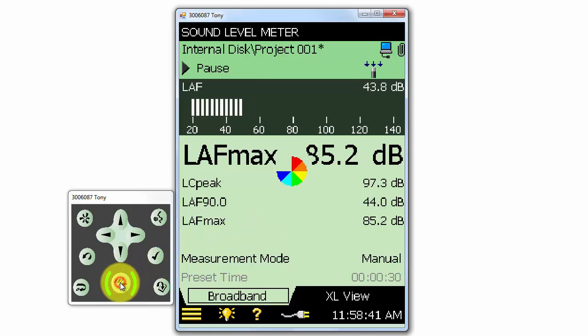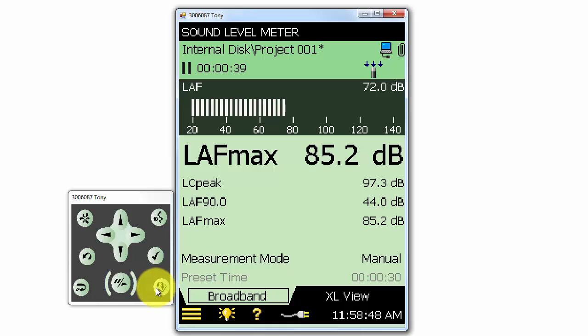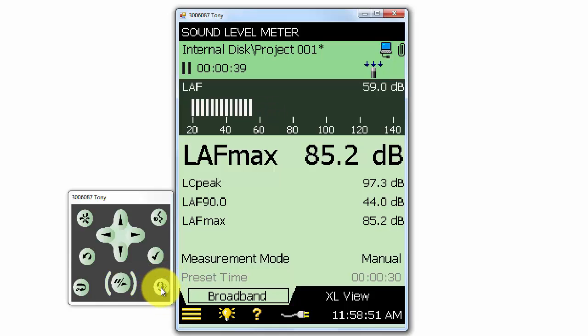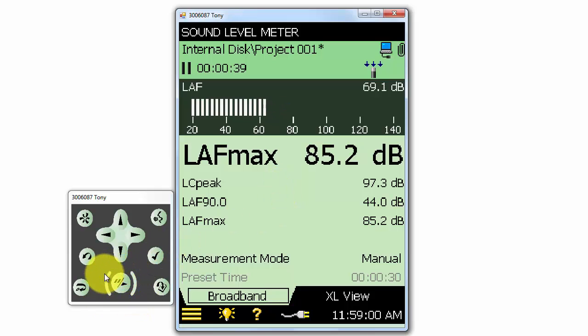If I stop the measurement and want to save it, I can click on the save button to the right of the play pause button. Notice that before I save the measurement, the indication light around the play pause button will blink quickly to indicate that the measurement has been made but has not yet been saved.